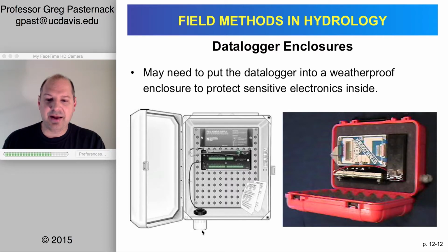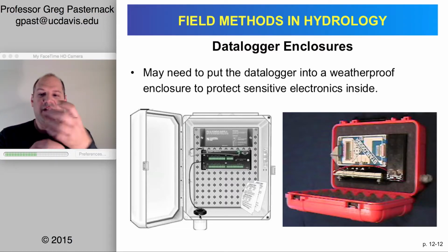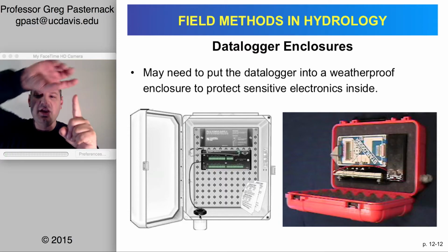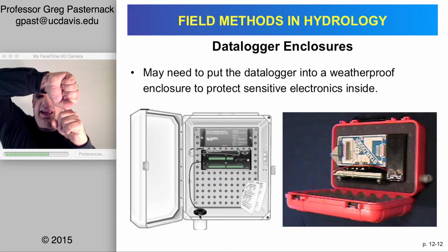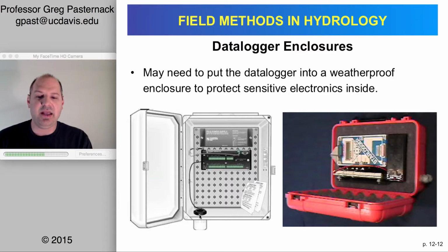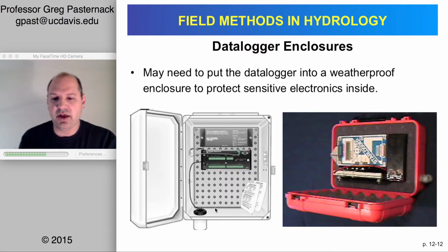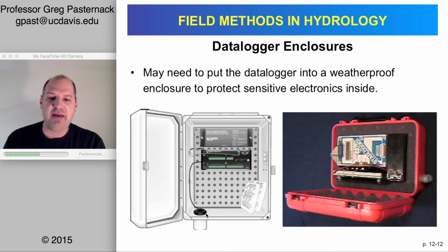You could also see at the bottom here there is an opening that allows sensors to go through. Usually these have screw-on press fit fittings, so that if this is a cable, if my finger's a cable, it's going to be able to squeeze tight on that so it can go through, but it's going to be a tight fit. And the one on the right with this red box, you'll see two gray knobs on that. That is another one of these tightening fittings, with a rubber gasket to seal it. And there's two, one for each sensor, whereas the one on the left is just one large opening, and you have to put as many wires through that as you need.